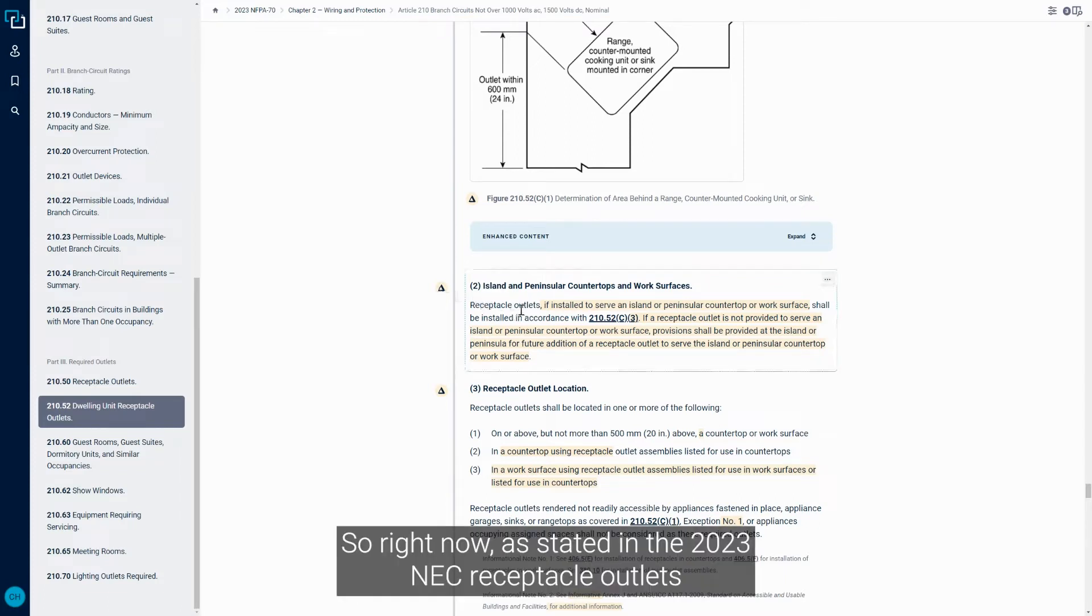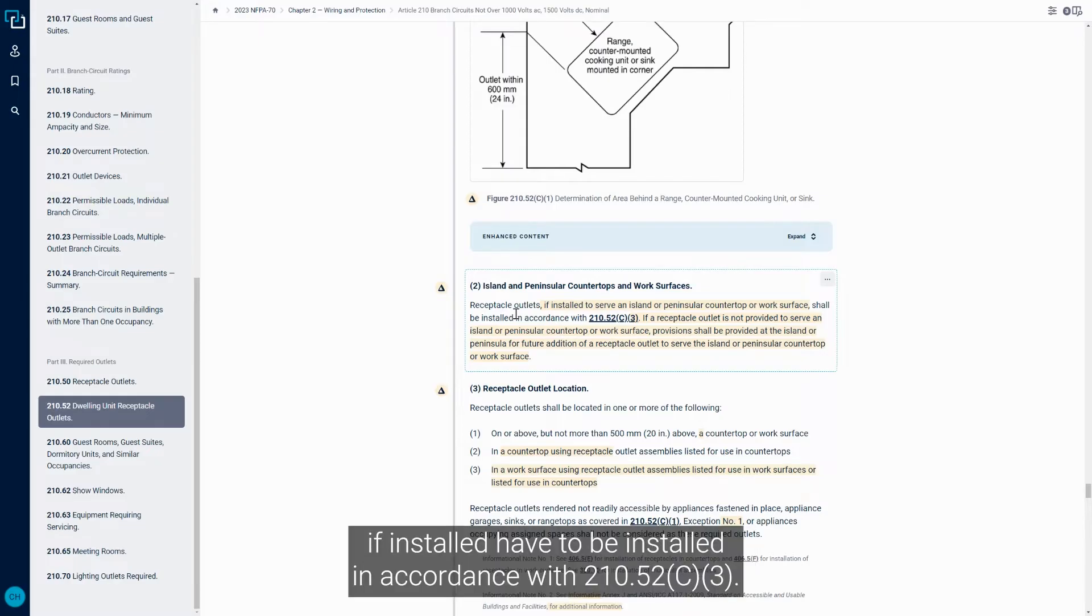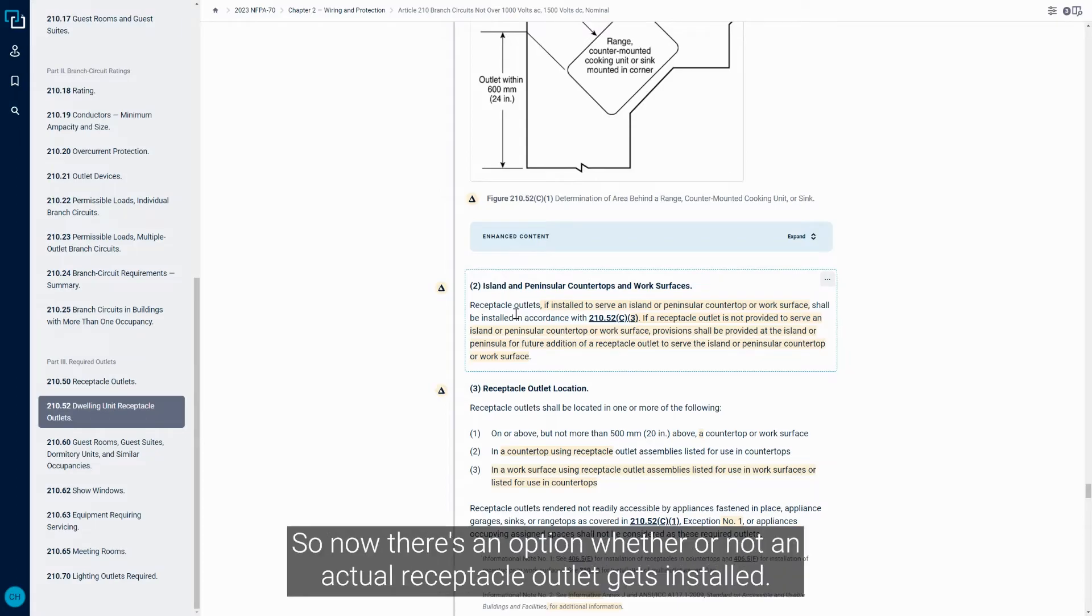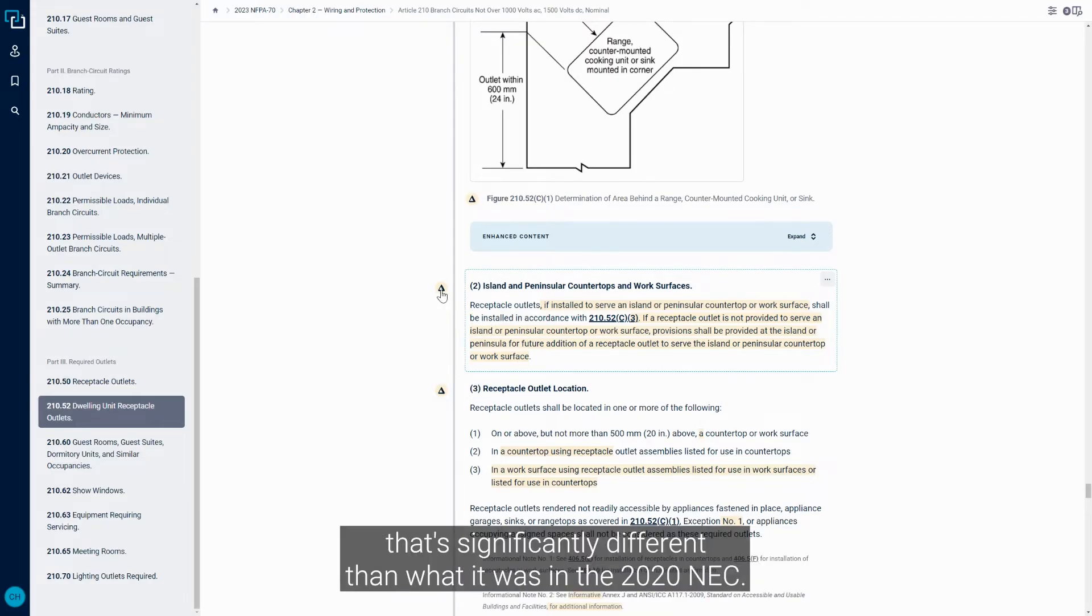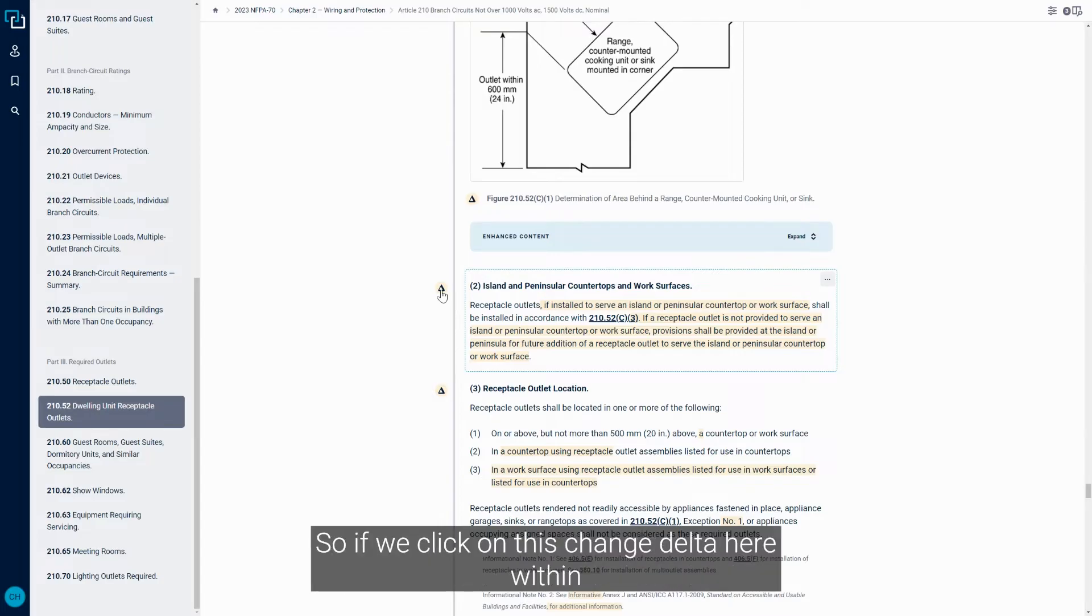Right now, as it's stated in the 2023 NEC, Receptacle Outlets, if installed, have to be installed in accordance with 210.52c3. So now there's an option whether or not an actual Receptacle Outlet gets installed as far as the 2023 NEC. That's significantly different than what it was in the 2020 NEC.